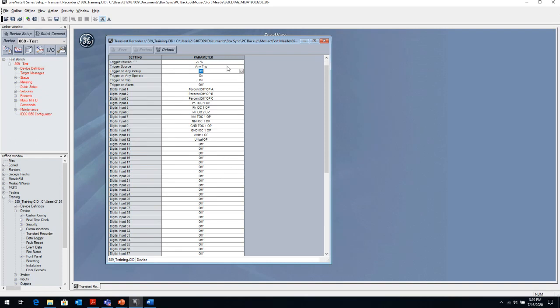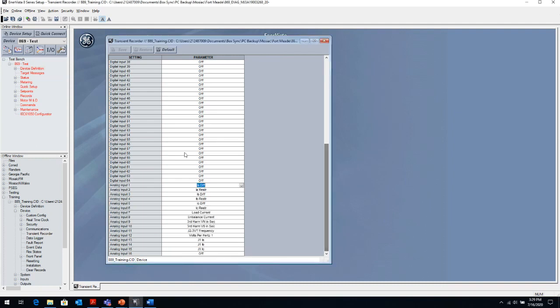So what do you want to see in the oscillography so that you can align what's going on in the power system to what's going on in the relay? And then you have some analog values that you can set. These are filtered measurements in the relay or calculated measurements in the relay. And these can be various different elements, and we have up to 16 of these analog elements that you can program.